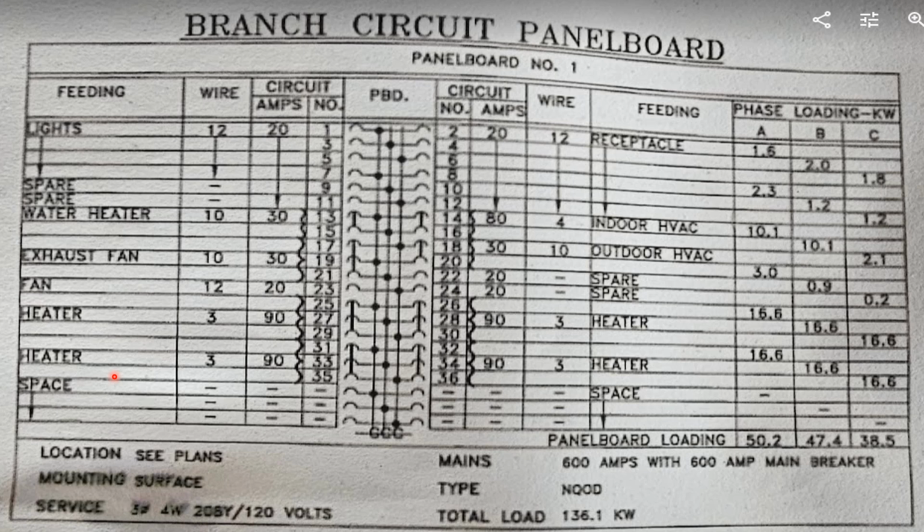And what you'll find, if you send a picture like this to your power company, or the people that you buy your parts from, you'll find that they can actually build you a panel directly from this panel schedule. And they will take a look at it and they'll make sure you got all your breakers. They'll make sure you got your breakers already installed from the factory in the right spots. They can do a lot of work for you that you don't have to do just from this one picture. And the same thing for you. You can really do a lot of your estimate work right here from this one picture.